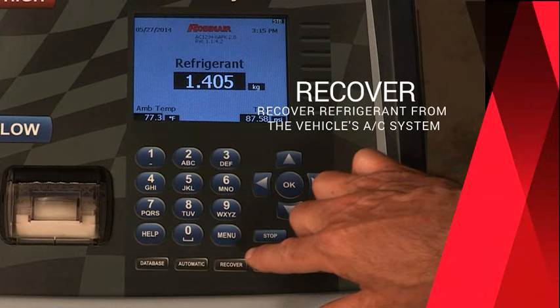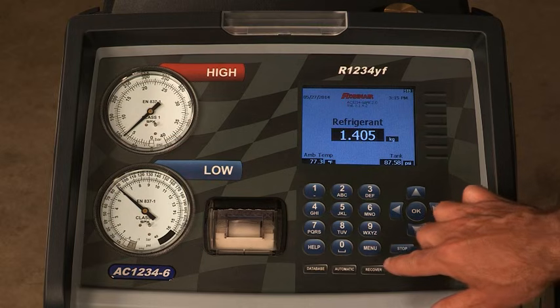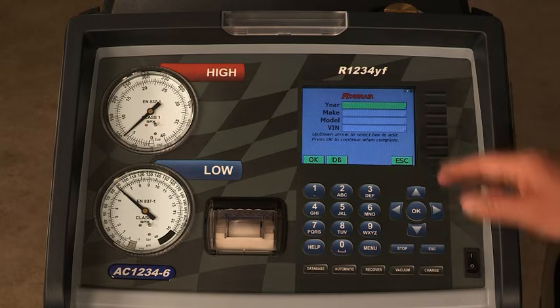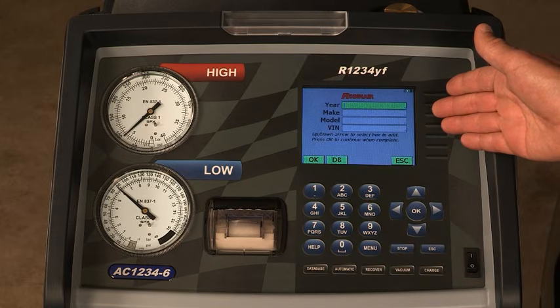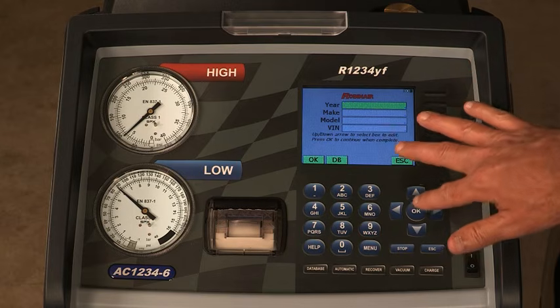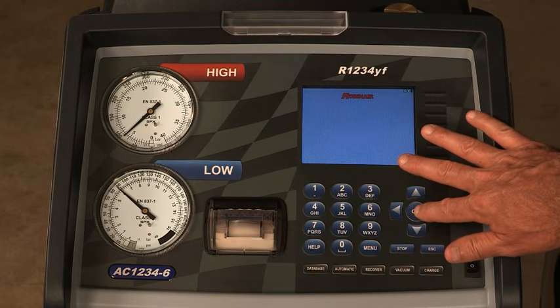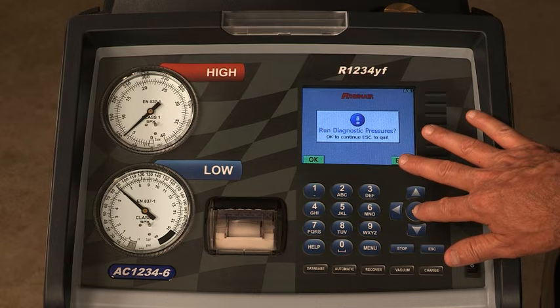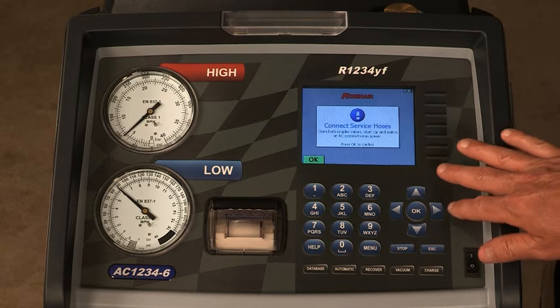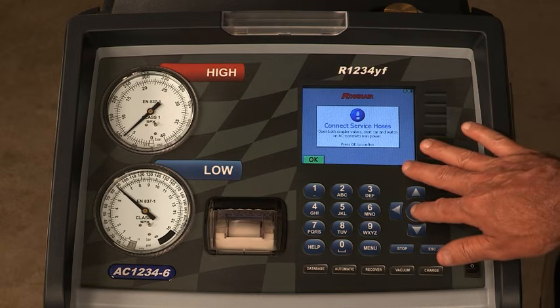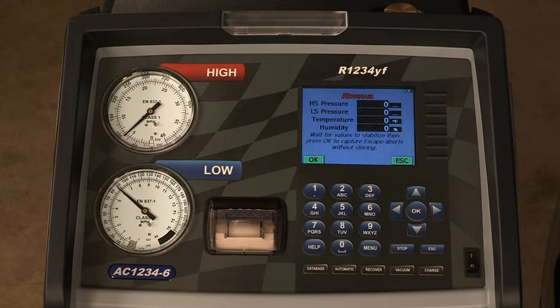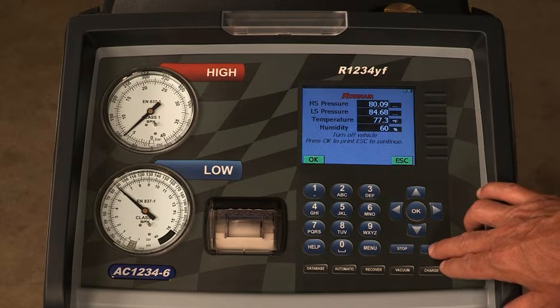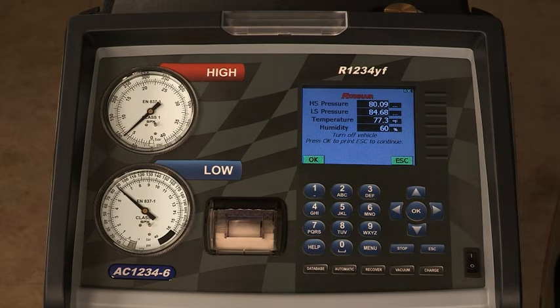Before starting a recovery process, you need to empty the oil drain bottle. Select the recovery function by pressing the recovery button on the control panel. Entering a VIN is optional. Press OK to skip this step and the machine displays Run Diagnostic Pressures. Press OK. The machine displays when to capture the values and when they may be printed.